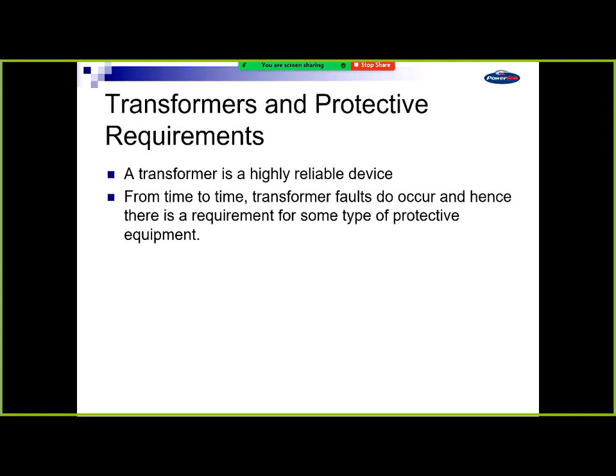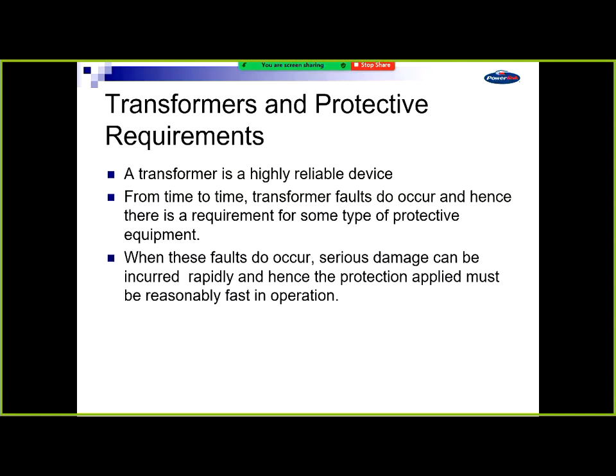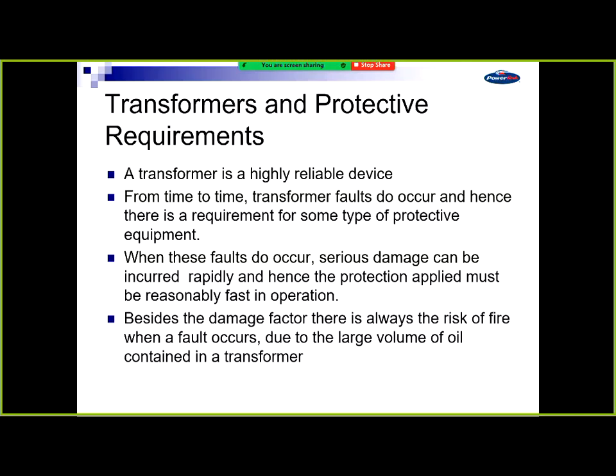So transformers are highly reliable. We don't have many transformer faults, but they do occur and you do need to protect them. In fact, all plant items under the National Electricity Law need protection. If you don't have protection on the item, you've got to take it out of service. When faults occur, they can be quite damaging, some of them, some not so much. And you must provide the speed. We've got the rules for how fast we've got to clear them.